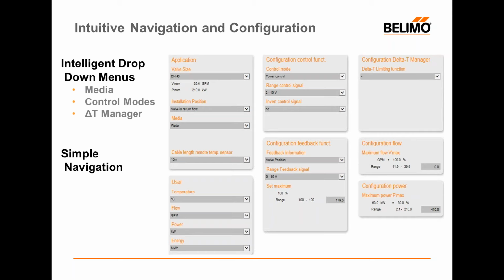To the right on the top, that's where we would select our delta T limiting function. So if you do or don't want to use the delta T manager capabilities of the valve, that's where you would turn it on. Below that, configuration flow would be associated with the flow control mode, so you would give it a maximum flow rate. Configuration power would be associated with power control mode. And what we don't see pictured here is a delta T set point. So if you do select delta T manager or delta T manager scaling, it will ask you for a specific set point for that functionality.